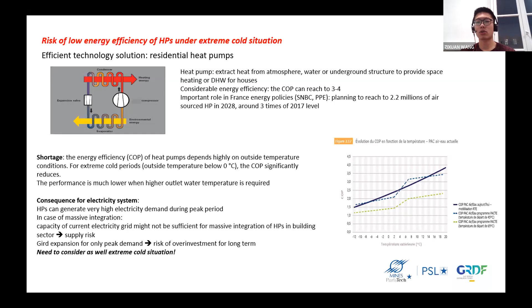So under this context, we have the hybrid heat pump as an alternative solution to the conventional standalone heat pump. A hybrid heat pump is composed of a smaller heat pump unit, usually 5 to 7 kilowatts in terms of electricity capacity, and a condensing boiler. So compared with a standalone heat pump, this solution can switch energy input depending on, of course, energy efficiency. Usually in extreme cold situations, the hybrid heat pump will use only the gas boiler. And when the outside temperature is higher, it switches to the heat pump.